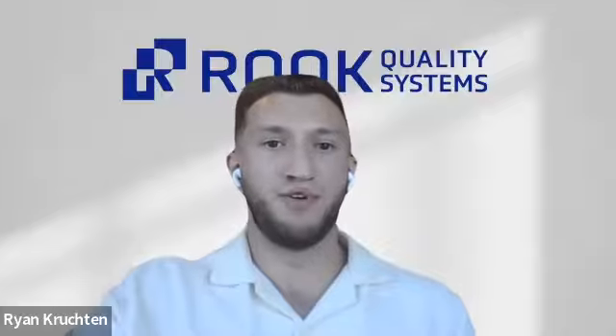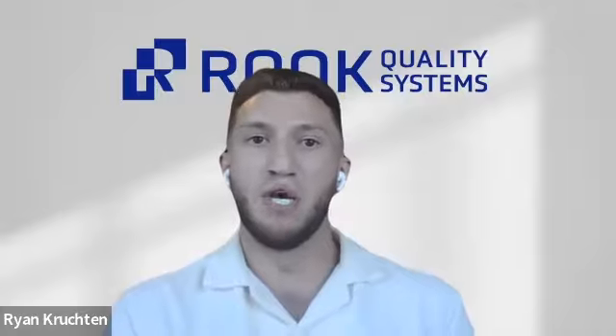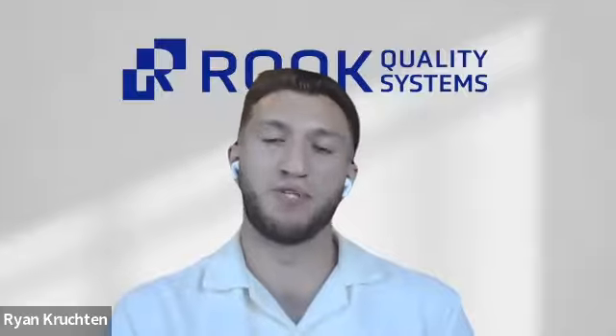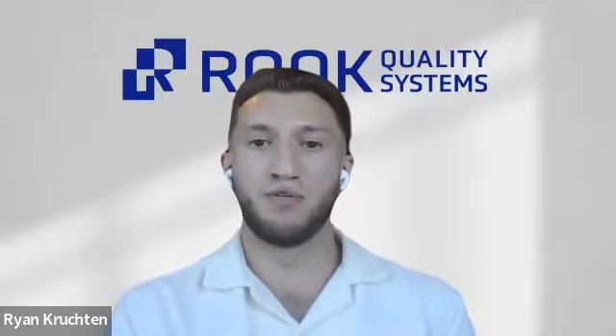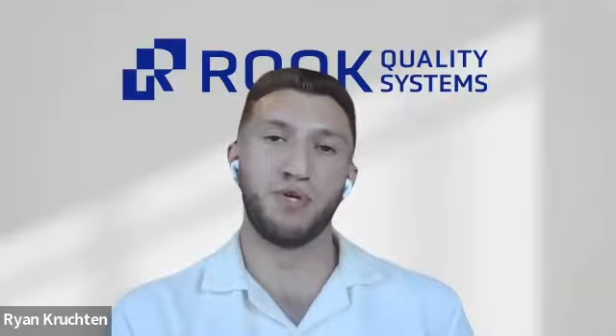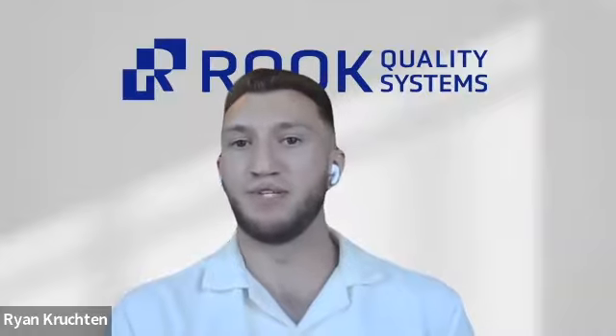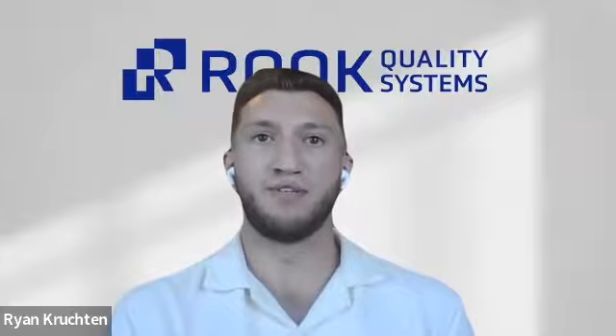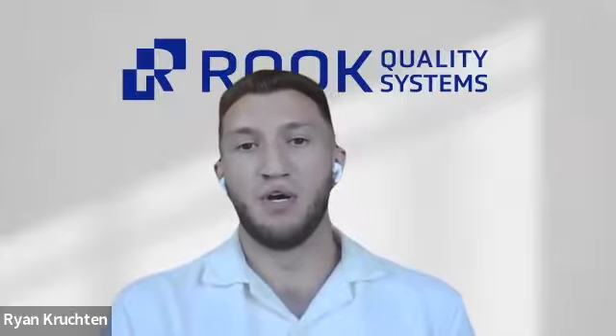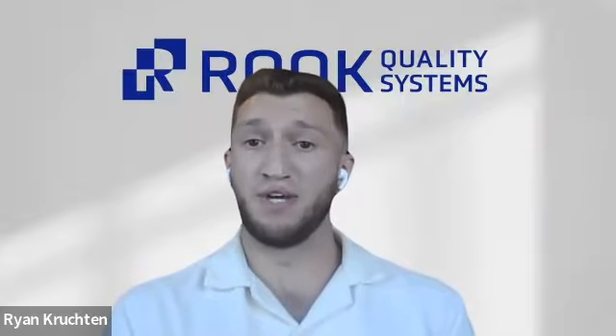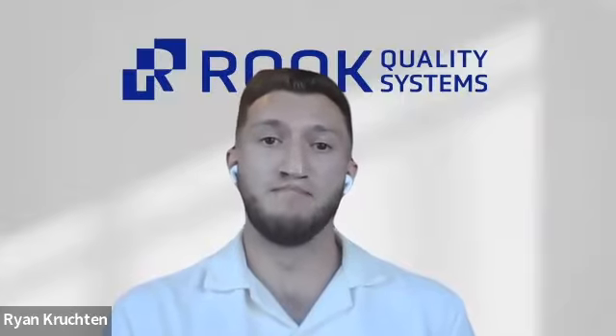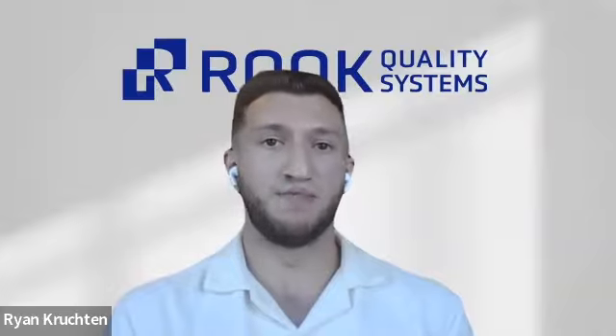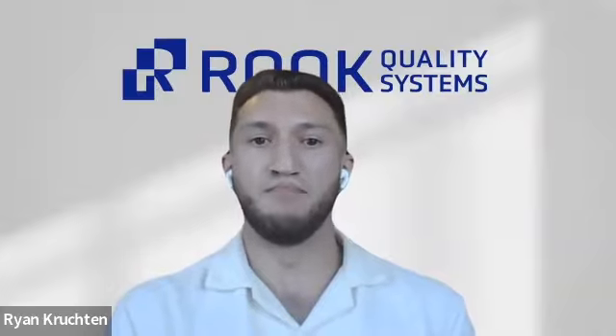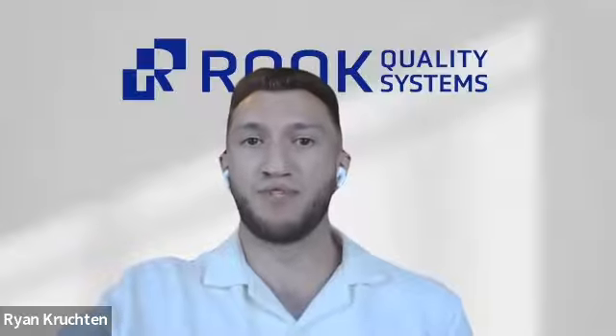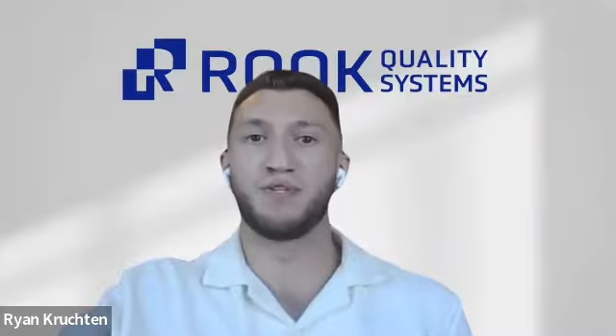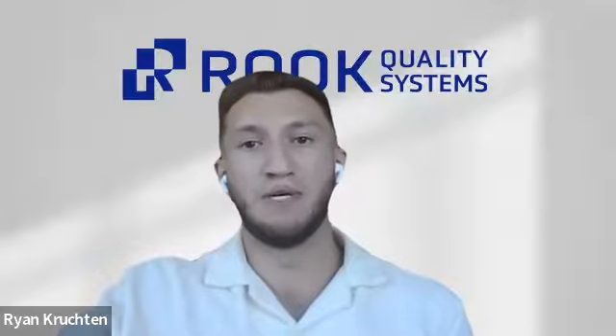The final pre-market cybersecurity consideration I'll cover is labeling. And the FDA has lots of questions about cybersecurity labeling. So the intent is that we need to communicate the security profile of the device to customers so that they can safely and effectively use the product. The list of labeling considerations is long, like I said, but I'll just mention some big ones. And these include device instructions and specifications related to the cybersecurity controls that are required for safe and effective use. So this would be like password requirements, use of a firewall, those types of things.